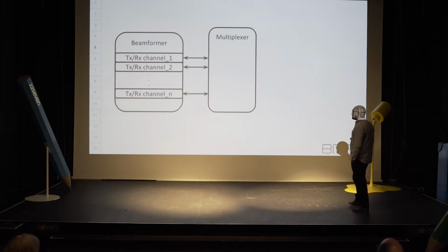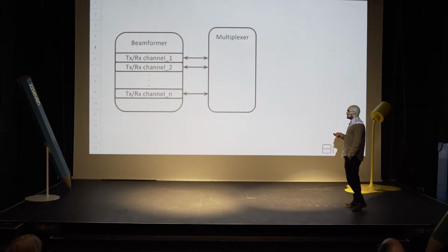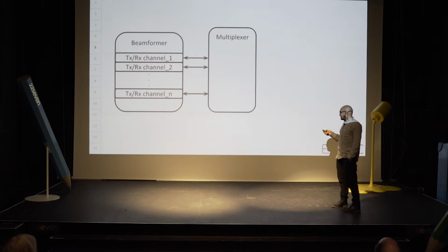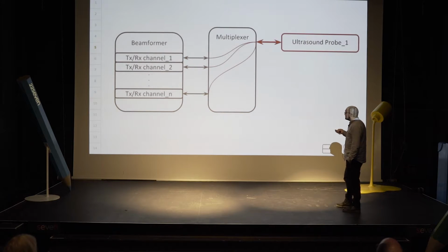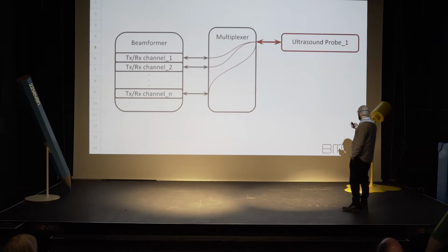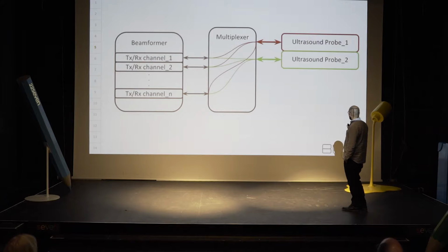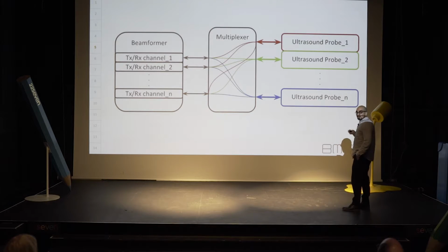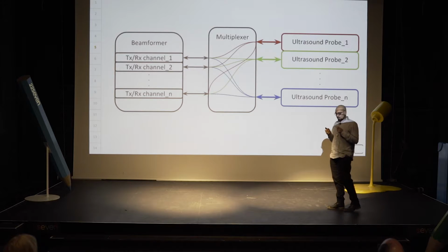Our first attempt was to increase the number of transmit and receive channels, and we did that using a piece of equipment called a multiplexer. The best way to conceptualize a multiplexer is an old switchboard operator who can connect one phone line to many other phone lines. So that's exactly what the multiplexer does. Here it connects all the transmit and receive channels to ultrasound probe 1 or ultrasound probe 2 or all the way through to ultrasound probe N. And what that allows us to do is to put many small ultrasound probes next to one another.